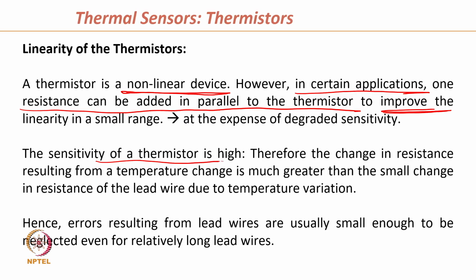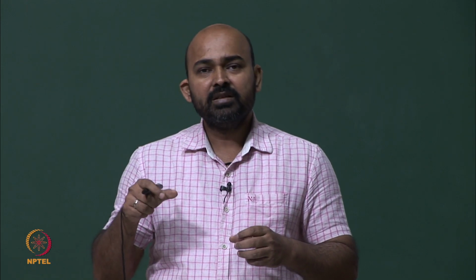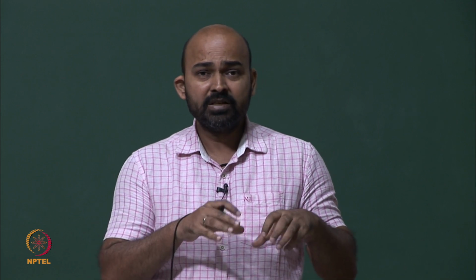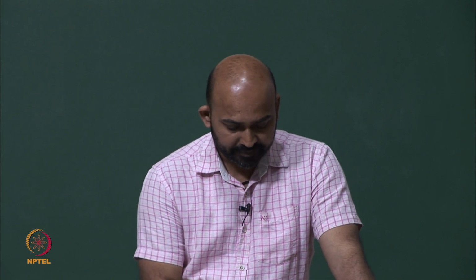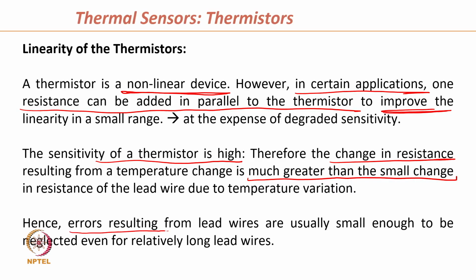The sensitivity of the thermistor is very high, therefore the change in resistance resulting from a temperature change is much higher than the small change in resistance of the lead wire. So, if we have a lead wire connecting this thermistor, the resistance change in the thermistor will be much higher compared to the change in the lead wire. So, we do not have much of a lead wire problem here. Hence, error resulting from lead wire is usually small enough to be neglected for thermistors.